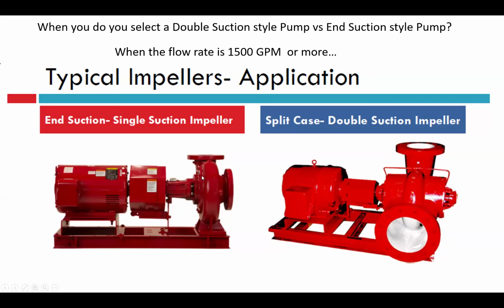Can you see selections with this style pump? Absolutely. But the wear and tear that pump is going to go through longevity wise and the service that's going to be required to keep that pump up and running is going to be different. It's a more expensive cost up front, but the reality is that split case double suction is a much more robust design to operate with that higher flow rate and not have these service issues.